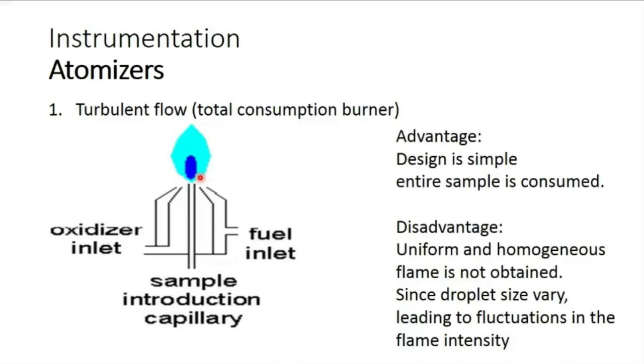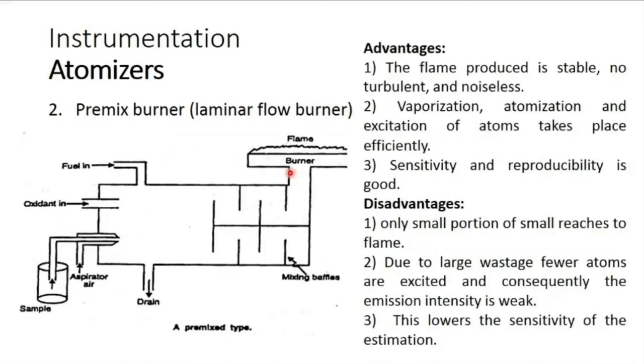Advantages of the total consumption burner: design is very simple, and the entire sample is consumed so a large quantity of sample is present in the flame. Disadvantages: a uniform and homogeneous flame is not obtained because droplet sizes vary, and since all droplets — large and small — enter the flame without any size selection, the signal is not uniform.